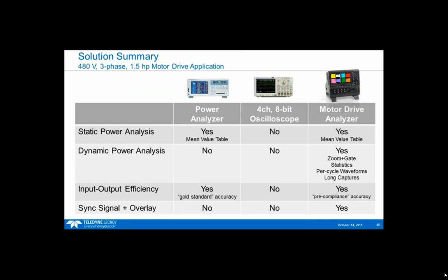Okay, so a quick solution summary here. We showed both a power analyzer and a motor drive analyzer can do static power analysis. The dynamic power analysis capability of this product is very rich - there is no corresponding capability here. The input-output efficiency, we do measure that, with what I call pre-compliance accuracy. If you're really trying to get a certificate for Energy Star or some government cert, this product will be a little more accurate - it's what we would call the gold standard. But a lot of times a design engineer just wants a pretty good idea of how things are changing over time, and we can do that within about 1.25% for efficiency. So it's still very good, but it's not the gold standard.